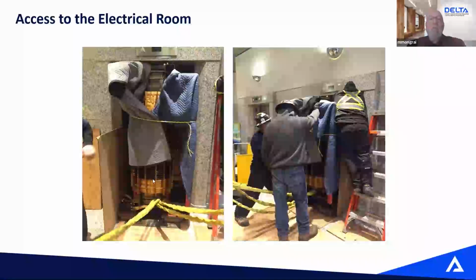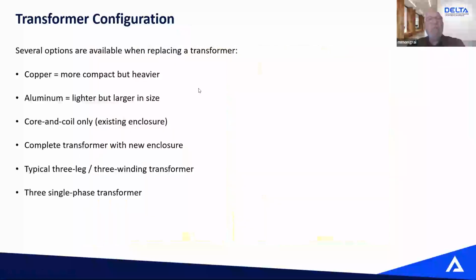But we had an idea of using the elevator shaft and bring the core and coil down in the third basement through the shaft of the elevator. So working with the elevator company, the Kone or ThyssenKrupp of this world, by knowing the capacity of the motor above, and not using the cage for the people, but just using the motor and the wires, what weight can we do? So knowing those sizes, we designed something that we were able to bring down in the electrical room.